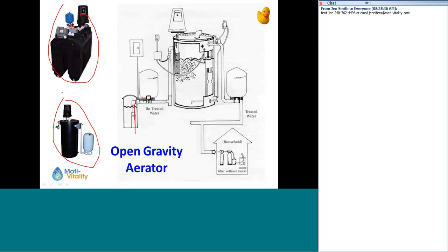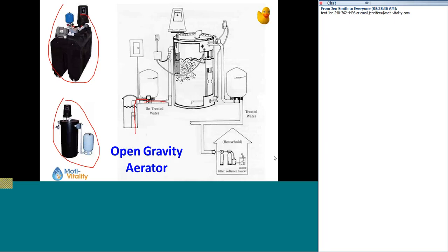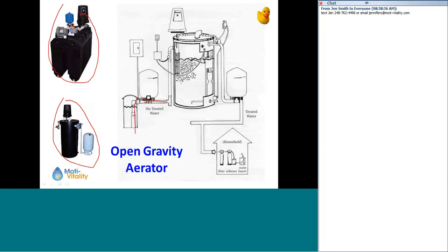And so you bring that water in, and this becomes essentially the well. Basically, it becomes the well, except it's got gas in there, and the gas spins out through this pipe. The gas that's in the water, let's say it's methane, or if it's dissolved oxygen or any kind of odor, will vent out through this vent pipe, which runs out through the side of the house. If it's something flammable, then it usually has to be above the roof line.